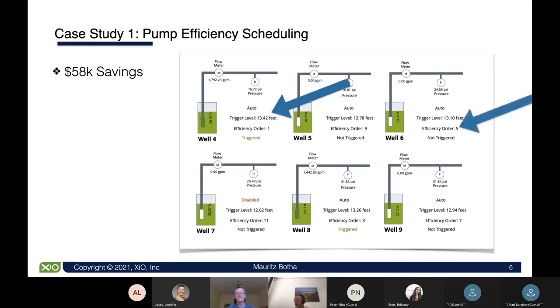The efficiency order is what we use on a daily basis. We calculate the energy intensity for each pump, which is the kilowatt hours required to produce 1,000 gallons of water. Based on that efficiency order, we prioritize the way these pumps come on. And then finally, people can take a specific pump out of service. The net result for this customer is we saved them $58,000 in just energy costs last year.